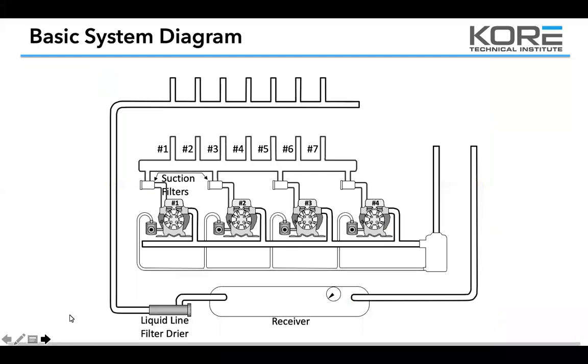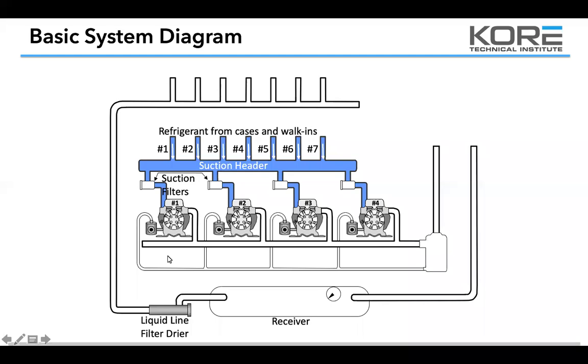Here's your basic piping diagram of the rack system. Refrigerant comes in through those EPRs. In the case, you're going to run that suction header at least two to four PSI lower than your lowest EPR setting. If you're running your suction header pressure too close to your EPR pressure — within a pound or so — you'll have a tendency with some valves to lock that valve up. Keep your header about two to four pounds lower than your lowest suction group to be safe.